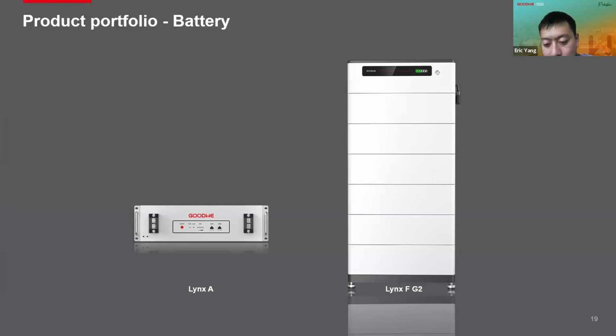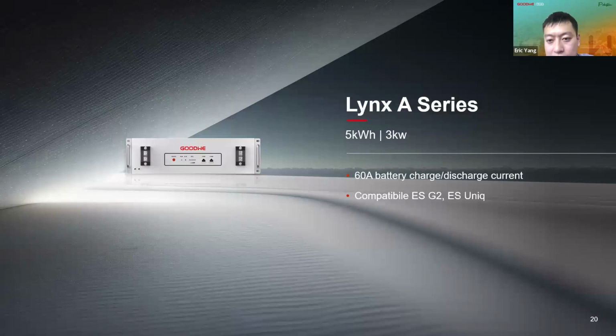See, the batteries that we already introduced with the inverters: we prefer the Lynx A series, which is the low voltage battery, and the Lynx F G2 series, which is a high voltage battery. The Lynx A series is a 5 kilowatt hour battery, and the discharge power is 3 kilowatts. It has 60 amp battery charge and discharge current, and it is compatible with GoodWe ES G2 and ES Uniq series. We think it is very suitable for the Pakistan market. Also, we are developing the next generation of the Lynx A series, whose charge and discharge current can be more than 100 amp.